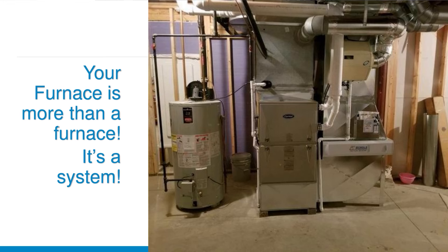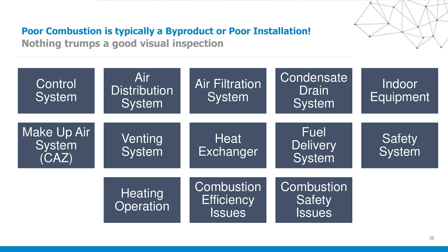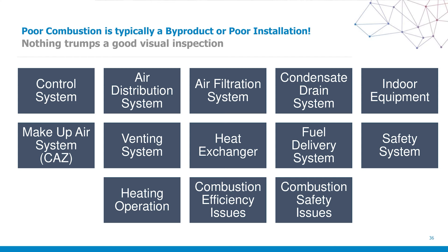Your furnace is more than a furnace — it is a complete system, an ecosystem in a living and breathing environment that changes continuously through different pressures, opening and closing doors, renovations, and the like. Poor combustion is typically a byproduct of poor installation. A good visual inspection will notice issues with the filtration system, filter tracks left open, control systems, make-up air, issues in the combustion air zone (CAZ), paint solvents sitting in front of an atmospheric system being pulled in. Things that relate to combustion safety — is the system firing correctly?